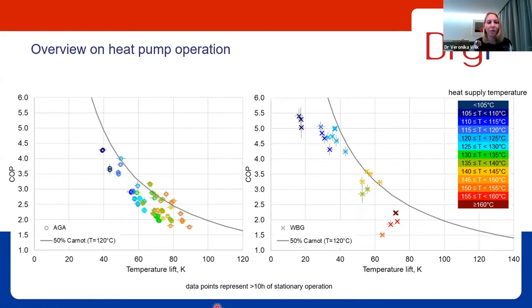For orientation, I've also included the gray line. This is an ideal heat pump that has a second law efficiency of 50% and a heat supply temperature of 120. So here you see the most basic relation. At the low temperature lift, we have a high COP, and at a high temperature lift, the COP decreases. And this is also true for the DryFiciency heat pumps.